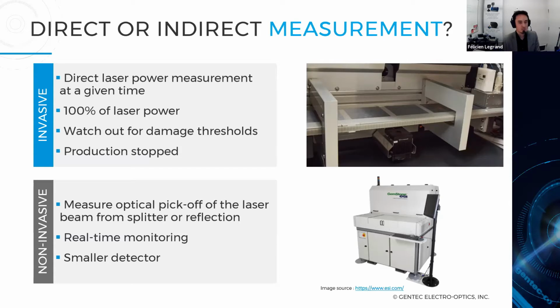What I call direct or indirect measurements are two possibilities. First of all, I call that a more invasive kind of measurement. It's a direct laser power measurement at a given time. You take 100% of your laser power, basically you block your laser beam before the delivery point for what your customer needs to do. And so you take a power meter that's adapted to this laser power, and of course, you watch out for damage thresholds, to be sure that the detector is adapted and that it won't be damaged by this laser beam. But then your production and your process, your research, is stopped because you're making a measurement. You file out a report, for example, and then you get back to production.